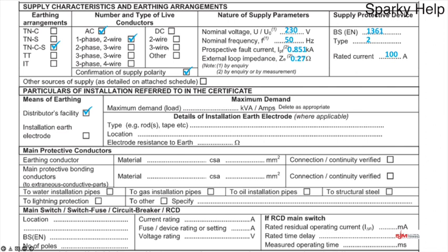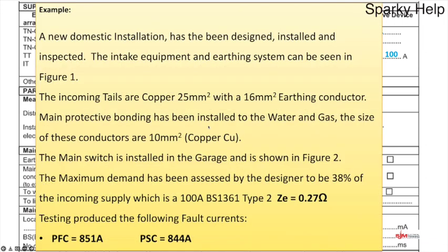Going across there, maximum demand. We need to go back to the designer for this, because maximum demand is a very contentious issue in most cases, unless we've all got smart meters, by the way. And if you've got a smart meter, watch out for this hourly billing and all the rest of it that's been coming up and will probably become more prevalent over the years as people transfer over to them. So in this case, looking at what the designer has given us, it says the maximum demand has been assessed by the designer to be 38% of the incoming supply.